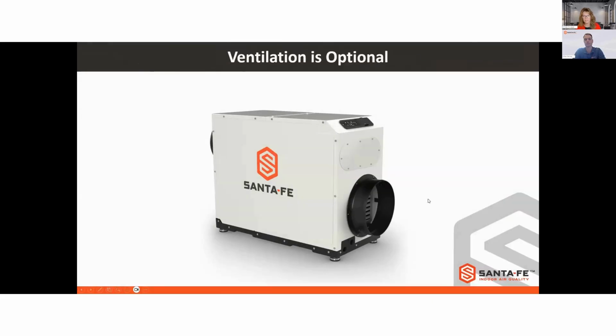Now, it is important also to mention that you don't have to use the ventilation on any of these units. Just like our prior whole house ventilating dehumidifiers that had the 6-inch ventilation duct, it's always optional. You don't have to use it. On the style here, the units will arrive with a plate over the ventilation duct in the box. And then on that V200, it's very similar to our older units with the 6-inch ventilation duct, where there's a damper inside that can be closed off.